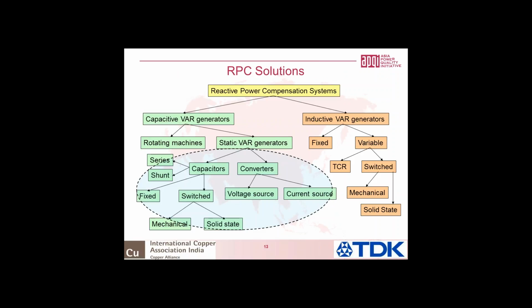They are much more than what you see on the screen. Basically, there are two major types. I've chosen to classify them as capacitive kVAr generators or inductive kVAr generators. Our primary focus would be more towards capacitive kVAr generators because most loads are dominantly inductive. So capacitive kVAr generators are of two types, rotating machines and static kVAr generators. And static kVAr generators could be capacitors, which could be series or shunt. Capacitors could be fixed or switched. When it is switched, it could be mechanically switched or through solid state devices. And when we have converter-based static kVAr generators, it could be voltage source or current source.